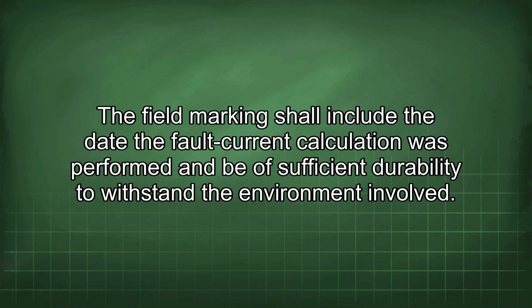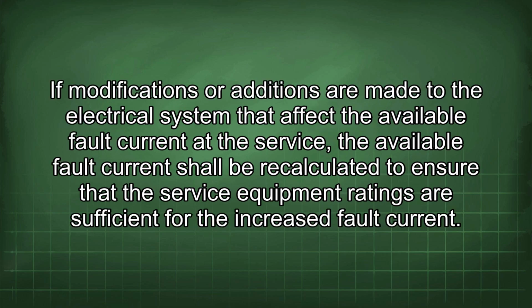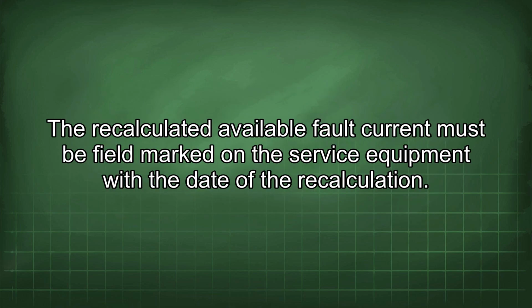If modifications or additions are made to the electrical system that affect the available fault current at the service, the available fault current shall be recalculated to ensure that the service equipment ratings are sufficient for the increased fault current. The recalculated available fault current must be field marked on the service equipment with the date of the recalculation.